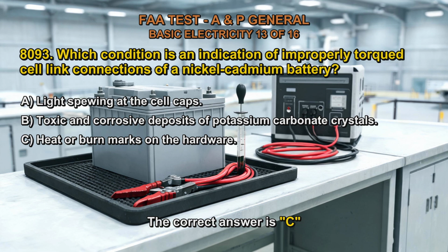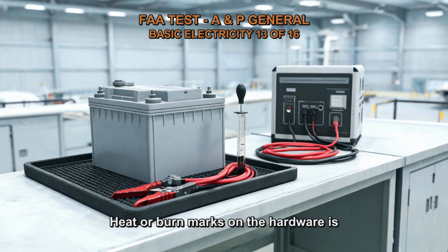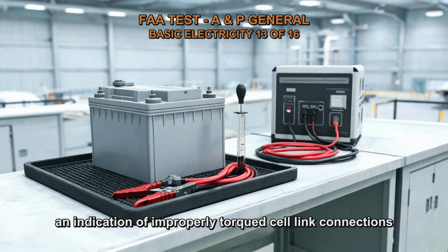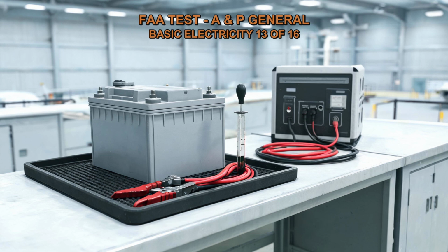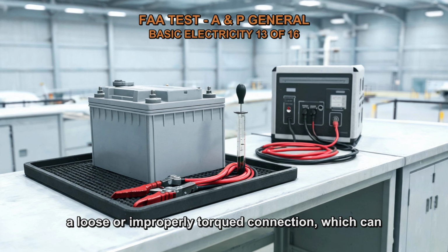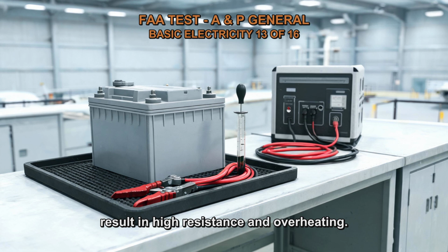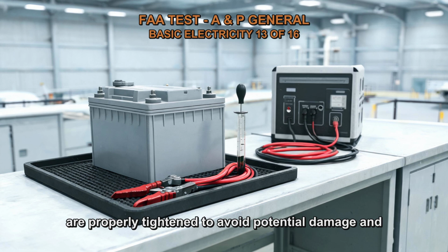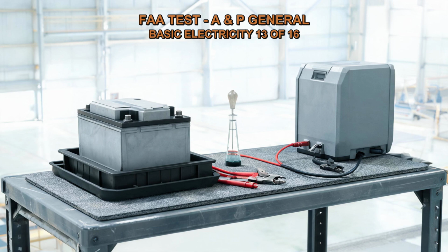The correct answer is C. Heat or burn marks on the hardware is an indication of improperly torqued cell link connections of a nickel-cadmium battery. If you notice heat or burn marks on the battery hardware, it may be due to a loose or improperly torqued connection, which can result in high resistance and overheating. It is important to ensure that all connections are properly tightened to avoid potential damage and safety risks.